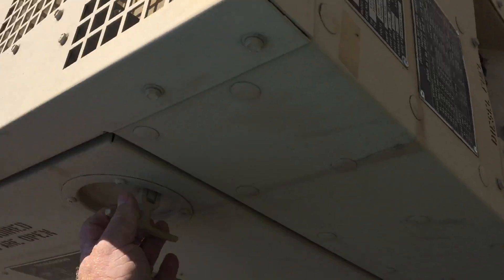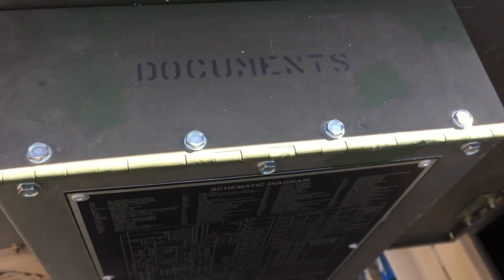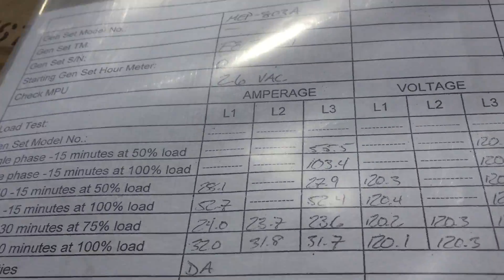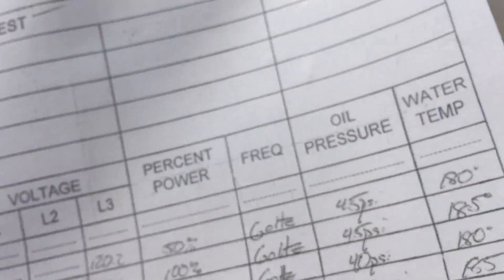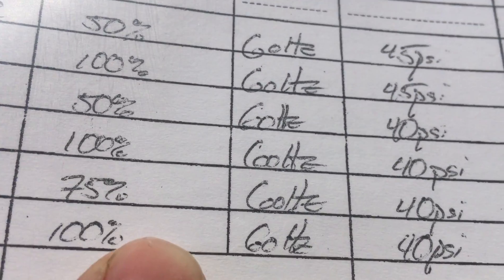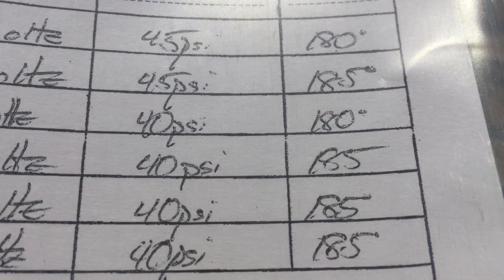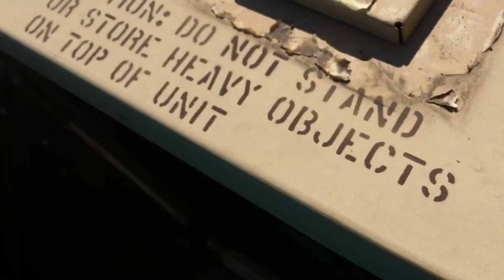There's a 24-volt NATO slave cable, a lifting diagram, and how to tie it down on a railroad car. It tells you you should wear hearing protection when you have the doors open. There's an electrical diagram in the document box. There are the papers, and here is the load test. It tells you all about it — 100%, 60 Hz, 120 volts, 40 PSI oil pressure, and water temperature was 185. Everybody's always asking about the load test — there it is.